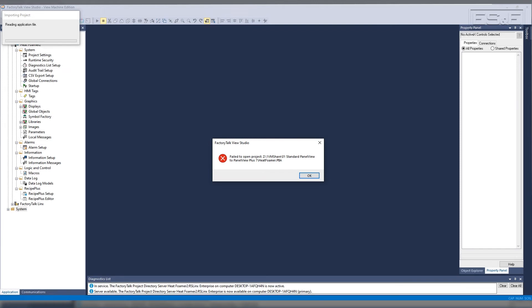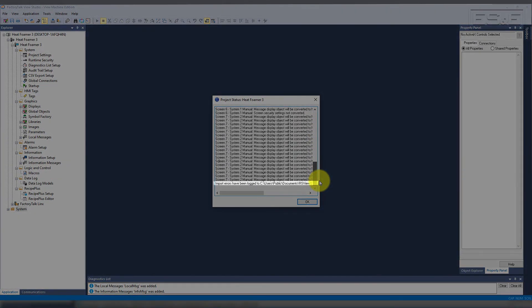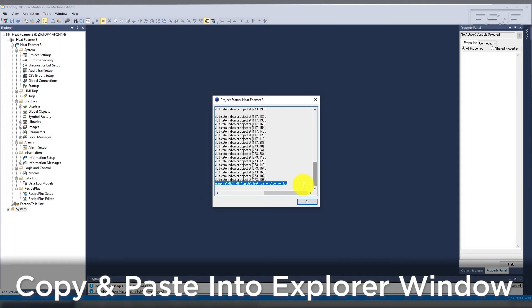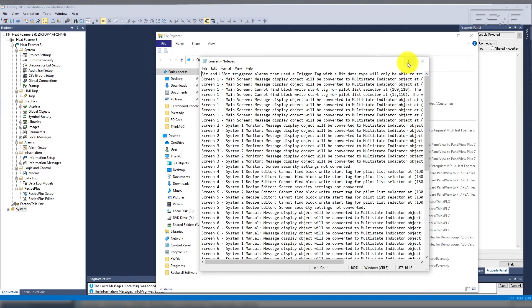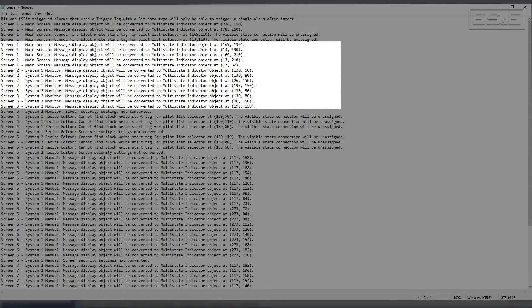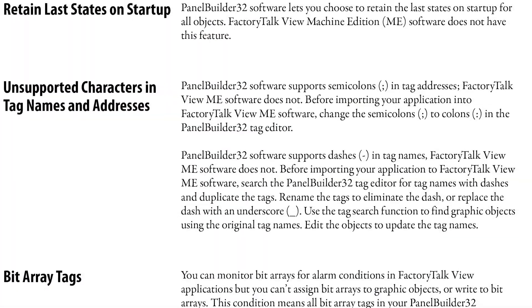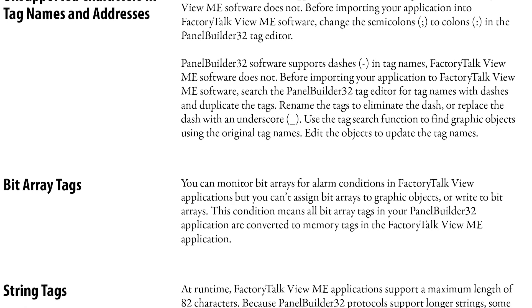Once the application is converted, the results of the import will be contained in the Project Status window. If you scroll to the bottom of the window, you can highlight the last line, which will have the path to the convert log. Copy and paste this into the Explorer window to bring up the convert log. Each of the entries in the log are items that potentially need to be addressed in the application — for instance, a message display object will be converted to a multi-state indicator object and requires no action. Entries that require attention are addressed in chapter one of the migration guide.